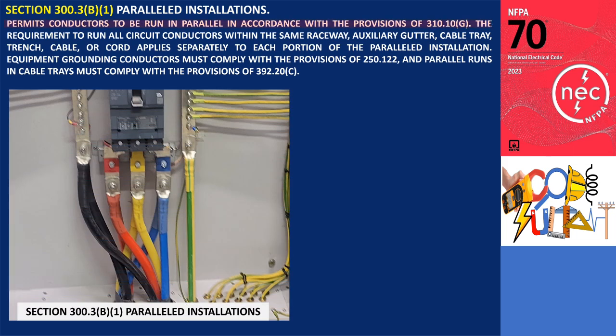Section 300.3b.1 permits conductors to be run in parallel in accordance with the provisions of 310.10g. The requirement to run all circuit conductors within the same raceway, auxiliary gutter, cable tray, trench, cable, or cord applies separately to each portion of the paralleled installation. Equipment grounding conductors must comply with the provisions of 250.122, and parallel runs in cable trays must comply with the provisions of 392.20.c.